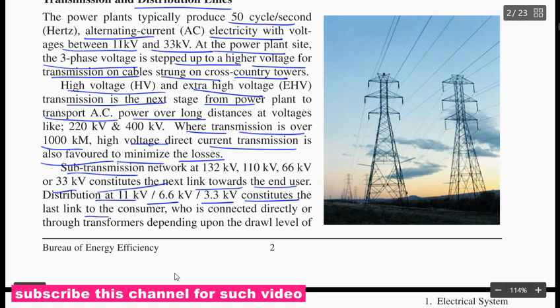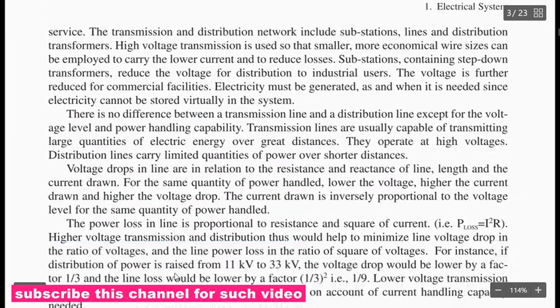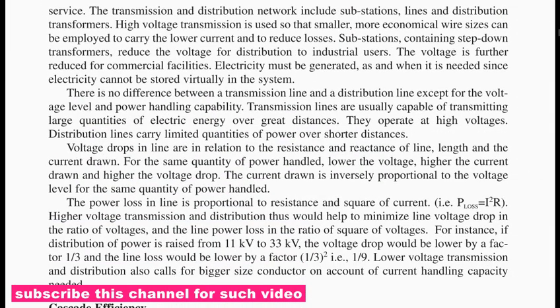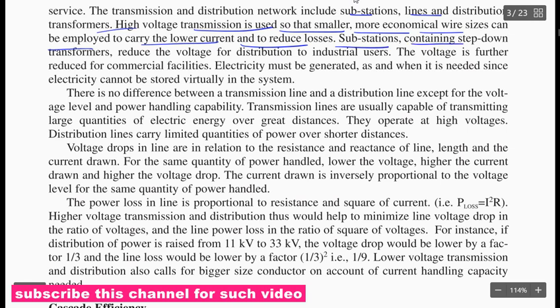Constitute the last link of consumers who are connected directly, or through the transformer, depending upon the draw level of service. The transmission and distribution network include substations, lines, and distribution transformers. High voltage transmission is used so that smaller, more economical wire sizes can be employed to carry the lower current and reduce the losses. Substations contain step down transformers, which reduce the voltage for distribution and industrial users. The voltage is further reduced for commercial facilities.